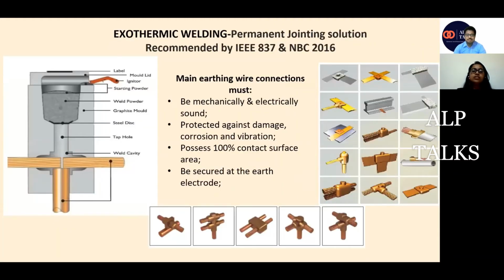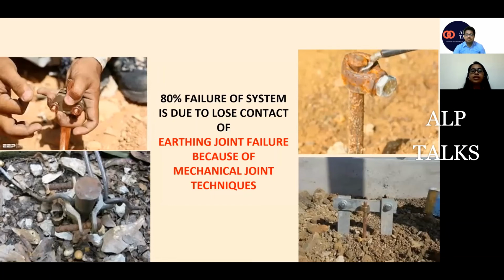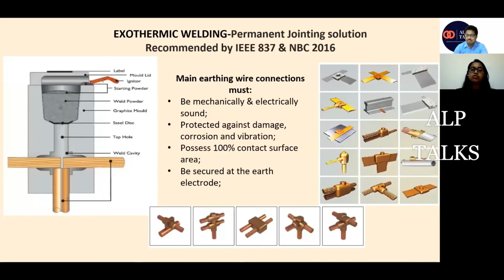Now coming towards the jointing system, as I have already told you, nut and bolt gets loosened with time, and they get corroded. With arc welding also there are many disadvantages. Like, we do not have 100% surface area because we overlap the conductors. So what happens is corrosion starts acting over the arc welding also. Because while we overlap the conductors, 100% surface area was not there. So due to the air gaps, oxidation occurs and corrosion starts acting upon the joints.